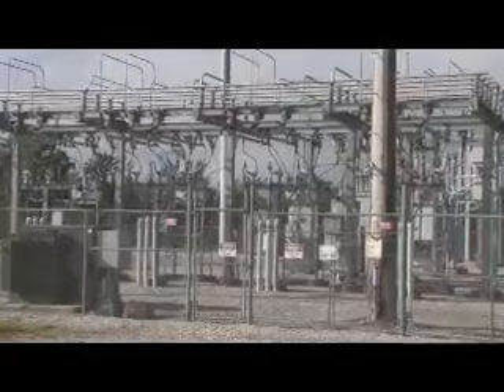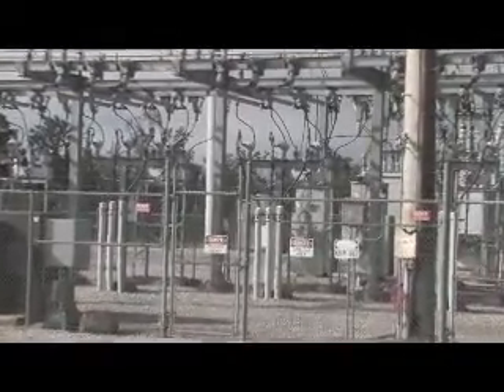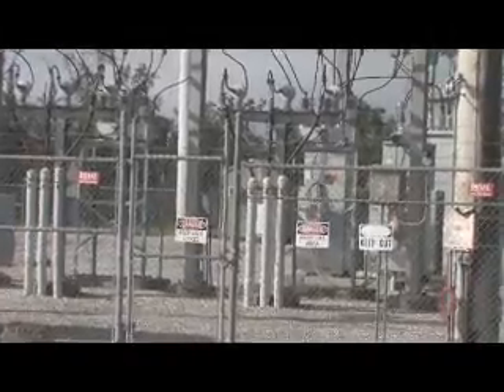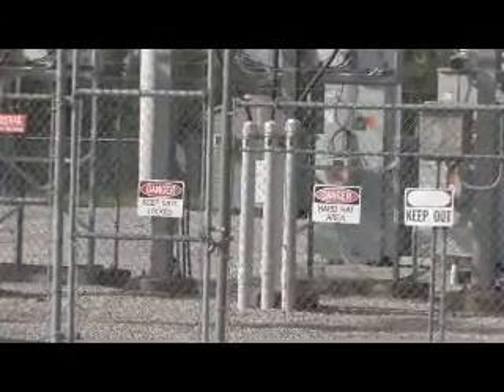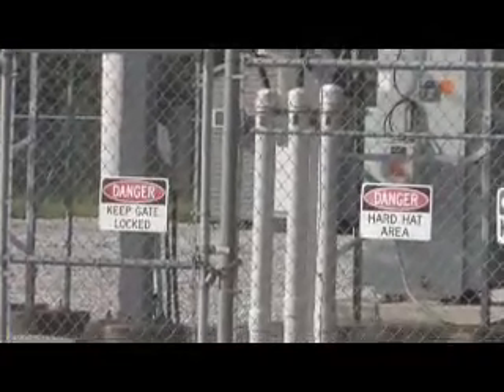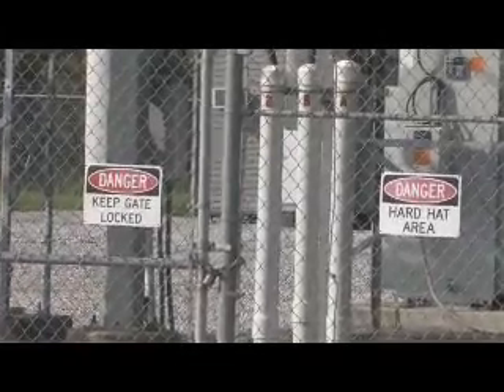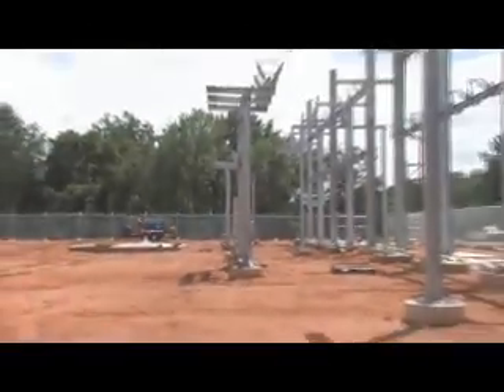You have to stage that. You have to bring it up in stages, starting back from the substation source, working out to the last person on that circuit. That takes some time. You have to bring on one section, make sure it holds, bring on another section, make sure it holds, and so on.